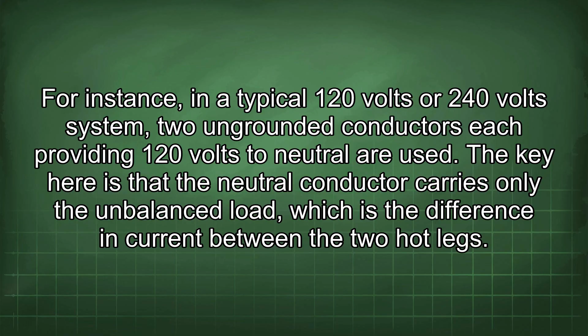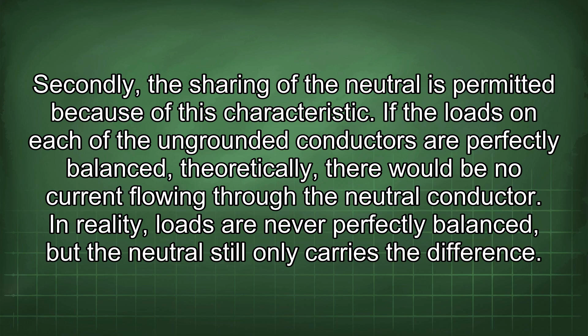Secondly, the sharing of the neutral is permitted because of this characteristic. If the loads on each of the ungrounded conductors are perfectly balanced, theoretically, there would be no current flowing through the neutral conductor. In reality, loads are never perfectly balanced, but the neutral still only carries the difference. This is why the National Electrical Code allows the neutral to be shared as long as certain conditions are met to ensure safety and proper operation.